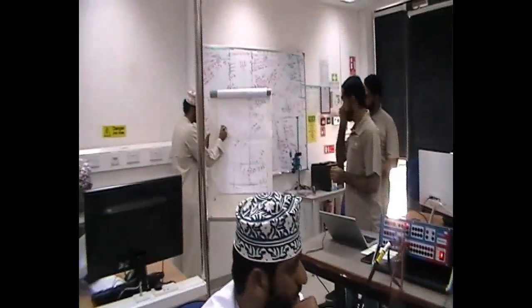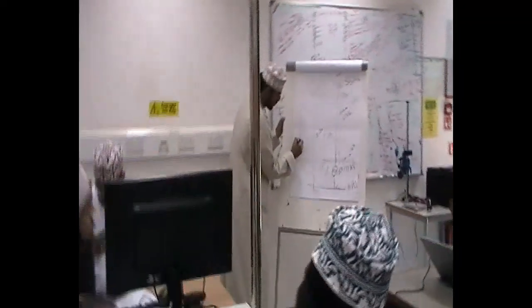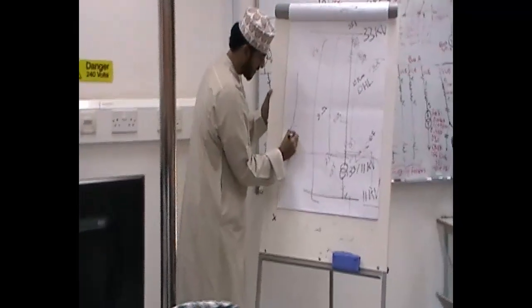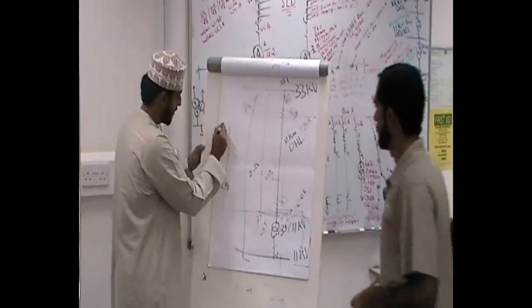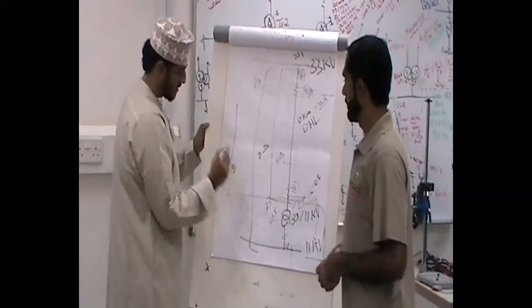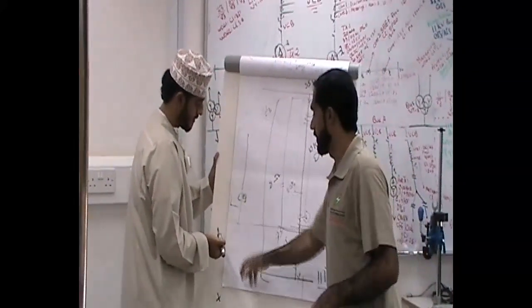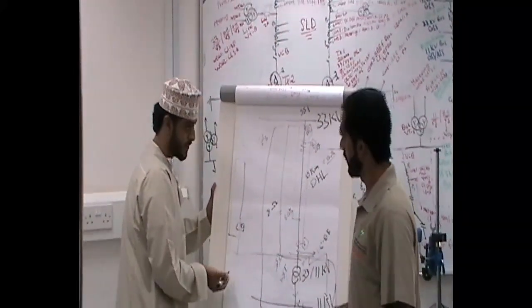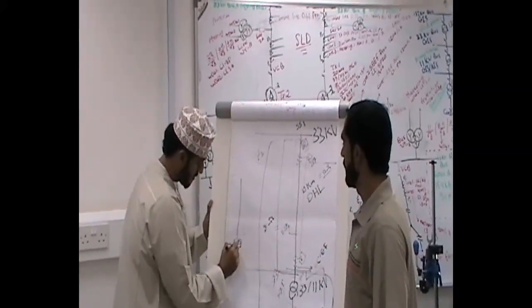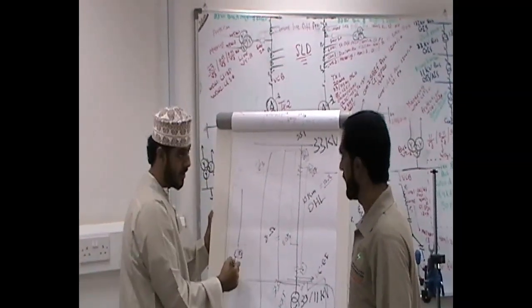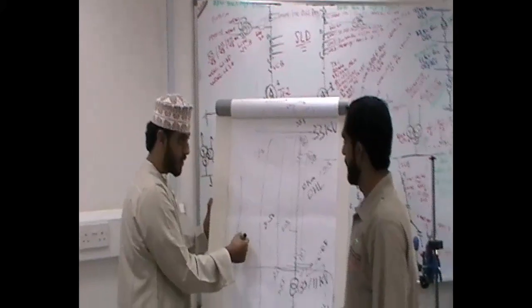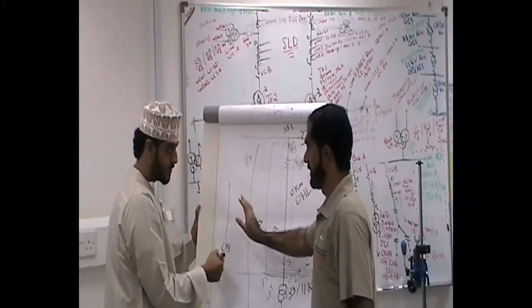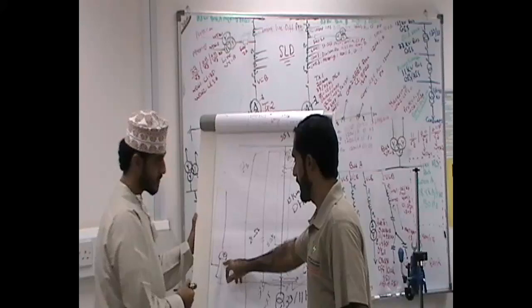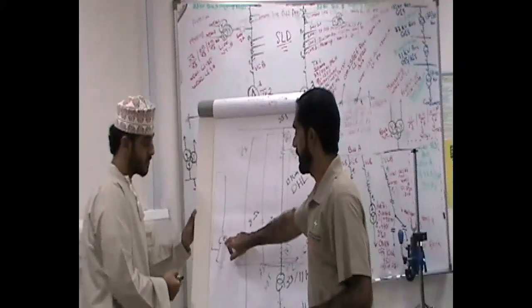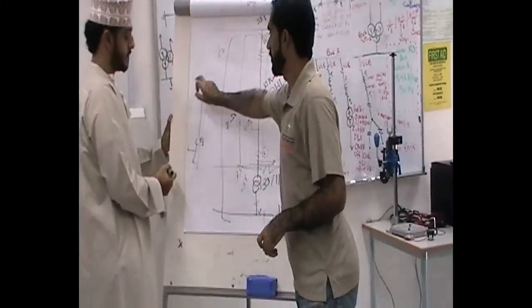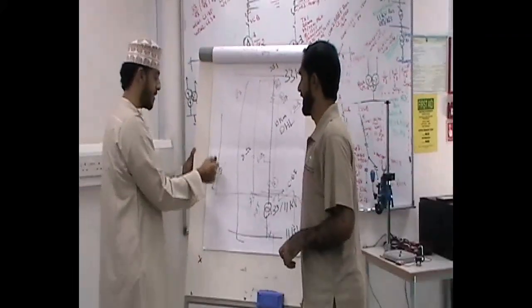In case there is another relay here. We have zone 3, for example, reaching until here. Zone 3 will go very, very far. For example, zone 2 will reach, and here is zone 1 for this relay. Zone 2 will be backup for zone 1 here. But zone 1 will not operate only if the relay is faulty. Then zone 2 will operate, so it will be backup in this case.